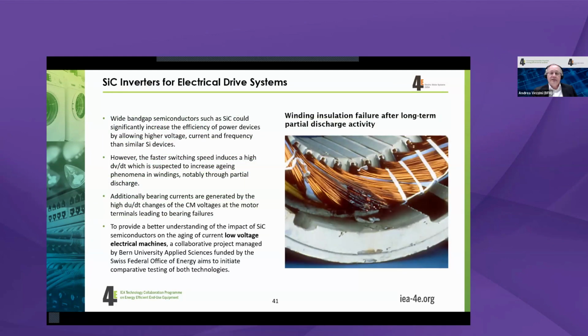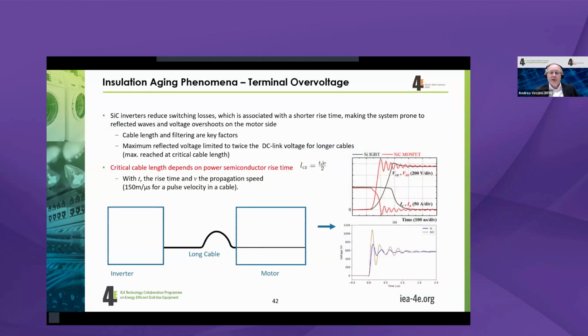And if you look at the two main failure modes which can happen, we see that the higher switching speeds could lead to winding insulation failures because you would have additional higher over voltage. The second point is the additional bearing currents can lead to damages on the bearings. We had similar discussions roughly 40 years ago with the introduction of IGBT semiconductors. But as you can see here, naturally the switching speed of silicon carbide is again much faster than with the silicon ones.